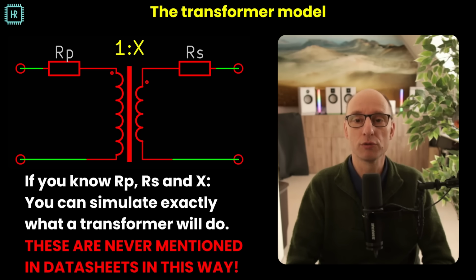The primary and secondary voltages are measured using two multimeters as you can see in the picture. Since grid voltages move around a bit, I always take a picture to make sure both readings are taken at exactly the same time. So dividing the secondary and primary voltages gives you X, the transformation ratio.